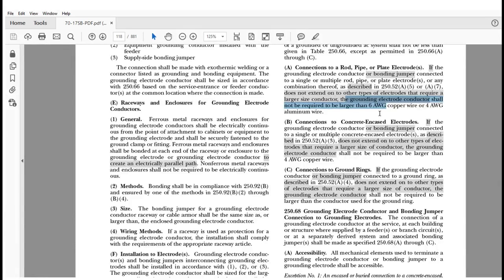Okay? So, made it pretty clear, got rid of that sole connection thing, good move. Basically, the term for it was replaced with the text. Okay, so the sole connection really was talking about daisy chaining grounding electrodes with a properly sized bonding jumper, because that's what we have. If we go to two ground rods and we go to the first one, that's the grounding electrode conductor. If we go from that one to the next one, say 6 feet away, then that is a bonding jumper. Okay, so it's kind of clarified now the terms to make it easier to understand.